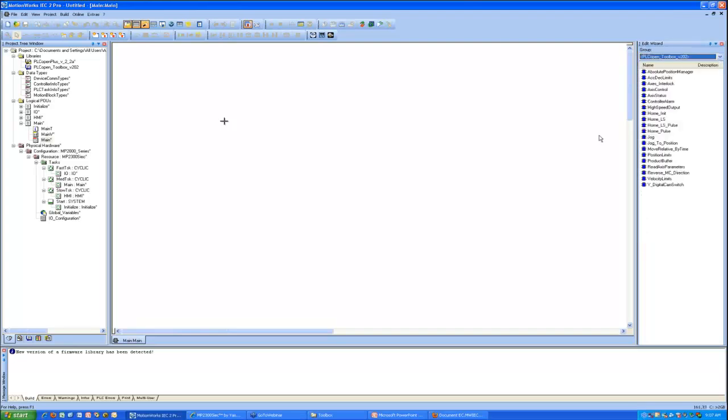You're going to see that we're going to have some typical problems come up. If I just try to compile this, I get a lot of errors. That would be expected based on the sequence of operations I just did. There's a lot of duplicate names, basically, of data types. That is because the toolbox itself contains a copy of two of these data type files that are also available in a new project template. The toolbox needs those data types because it contains many of the PLCopen function blocks, and so it serves as a basis for the PLCopen firmware library itself.